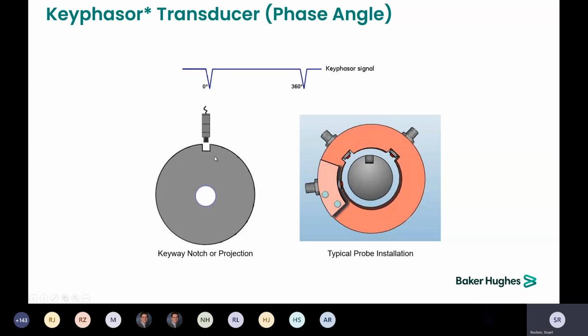With a projection, you do have to make sure that you roll the rotor to the point that the projection is under the tip of the probe. And if the projection is something like a key in a keyway, for larger shafts, you do need to make sure that the corners are rounded down on that outer surface, so that when you gap that probe in the center of the key, as soon as that starts to turn, those square edges of the key are physically further out from the center line of the shaft than that center mark of the key is. And you can either get into having a double pulse or actually physically breaking the tip again.